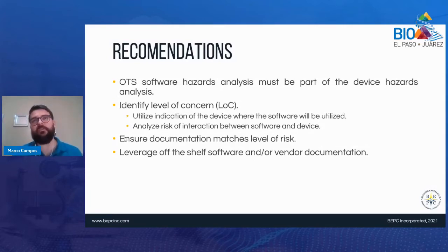I wouldn't recommend generating a very robust software validation for a simple medical device like a Band-Aid. But if you're looking at a very complex medical device with a high level of concern, then you need a very robust system in place with very robust validation. And the last recommendation would be: wherever possible, leverage off-the-shelf software and vendor documentation.